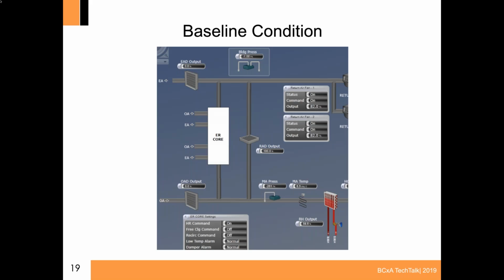So our baseline condition, this is the snapshot from the building automation system. You can see right now that in the very center, our return air damper is at 100%. And the return air opening is actually sized for 100% of the air handling unit's flow because when you're in full recirculation mode or free cooling, you need to be able to close that off or open that up or bypass for some reason as in recirculation to bypass to do 100% of the air. When you are not in one of those modes, you need to have that damper at a position that is not 100% to get your pressure drops. And that's what we'll start changing when we're doing our trials.